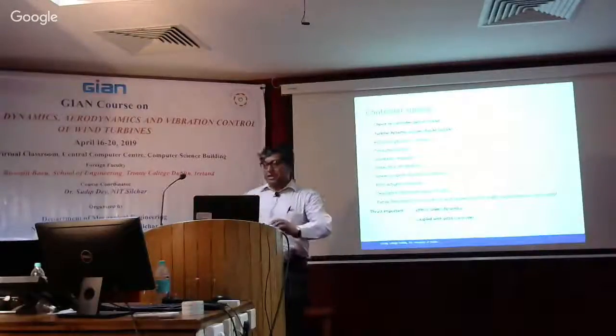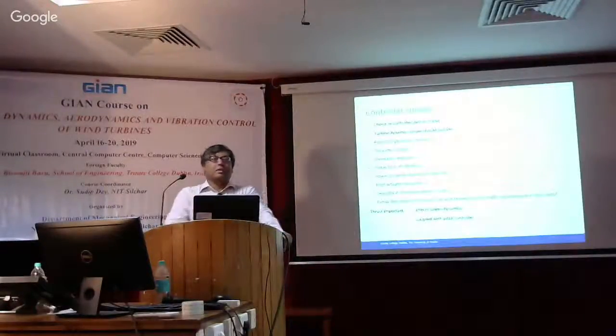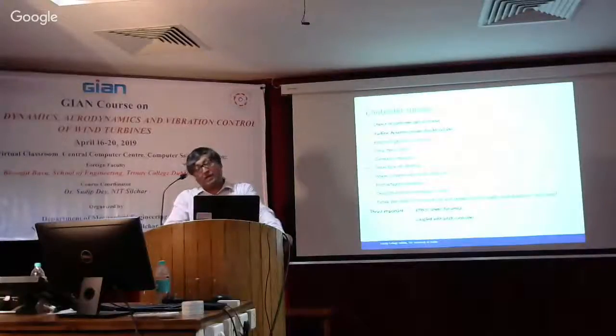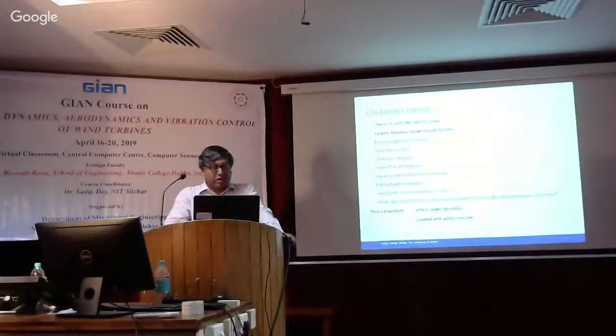Back in 2002 and 2003, people realized that suddenly there was not much wind actually there, but the towers were vibrating, and they called it flexing. That's why they were looking at bringing it into the grid code, the electric power grid code. What they found was that if there is an electrical fault in the grid, there's a propagation of that, and that impacts the vibration of the tower. Obviously, that means it is not entirely aerodynamic, but it contributes to the overall system dynamics.